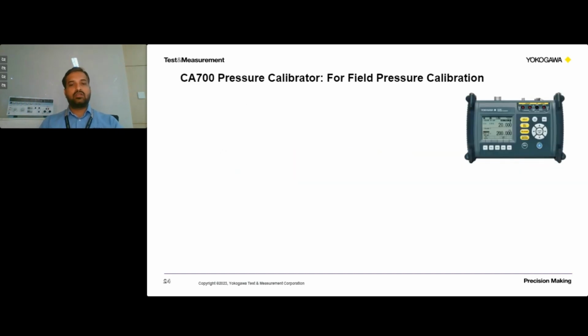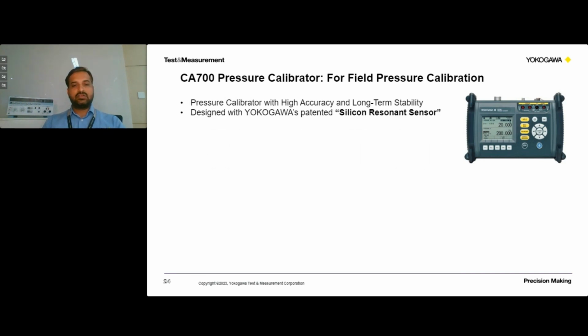Then we have got a model called CA700, and this is suitable for field calibration activity. As we discussed, this also has a silicon resonance sensor as a pressure sensing element. One of the main features of this product is that it has the capability to generate a report, and we can set the tolerance percentage in the calibrator. With that, a pass/fail report can be generated, and it can be decided whether the calibration done is okay for a particular step or not.